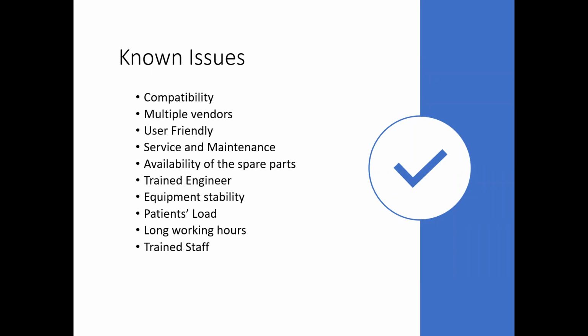Obviously, the patient load matters. If we are treating 100 patients, running our machine 6 days a week for long working hours, then the 4 preventive maintenance inspections in a year would probably not suffice for the needs of this equipment. So we will end up doing corrective maintenance, or we will end up increasing the frequency of preventive maintenance, for example from 4 to 6 or 7, and then certainly the trained staff.